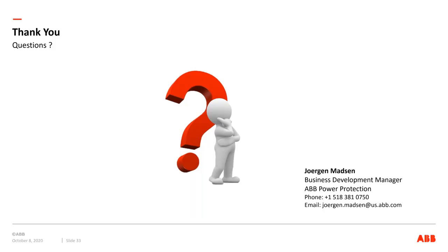Jürgen, does ABB actually manufacture any of these solutions? No. So ABB does not manufacture batteries. We use batteries in a lot of different applications, obviously with UPSs, and actually that may be a good question. Especially with lithium ion, we work very close with the manufacturers, or a couple of manufacturers, and we are not releasing anything to be installed with an ABB UPS without having gone through a full test with the UPS and the battery. We want to verify that everything works safely. Not only, of course, does the battery manufacturer have to do the 9540A testing, and then we do the full system testing, verifying that it works.